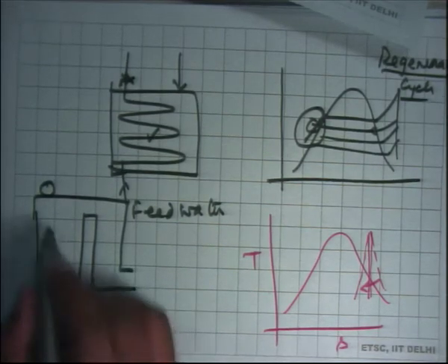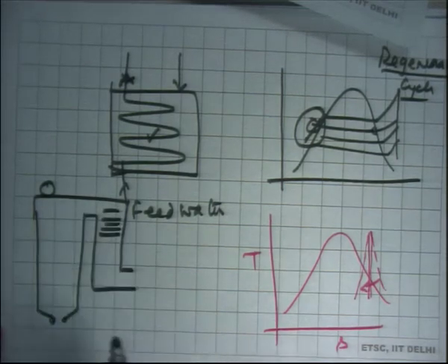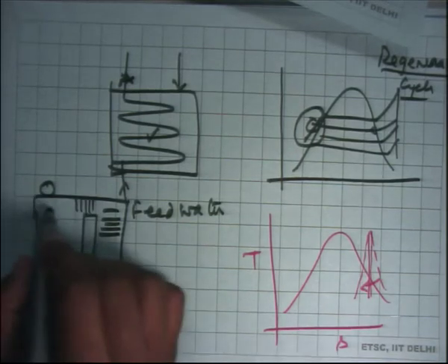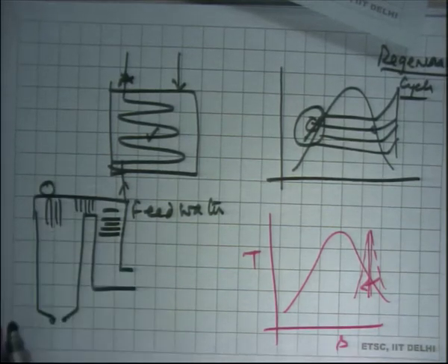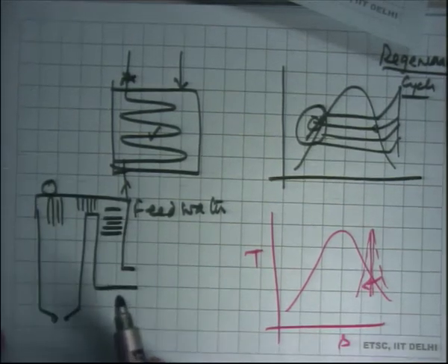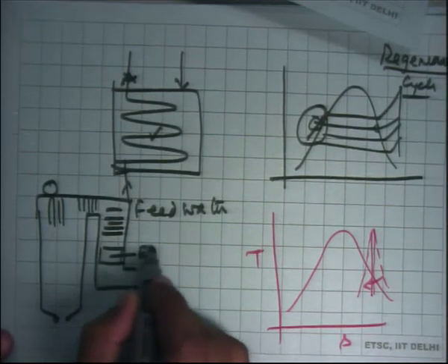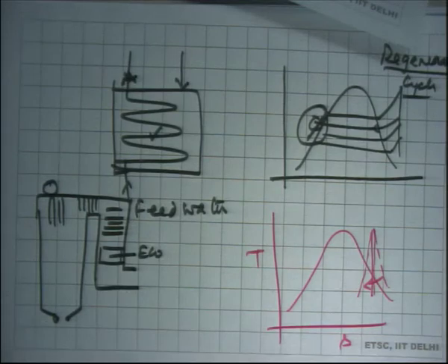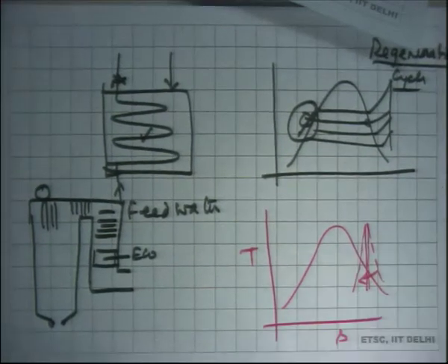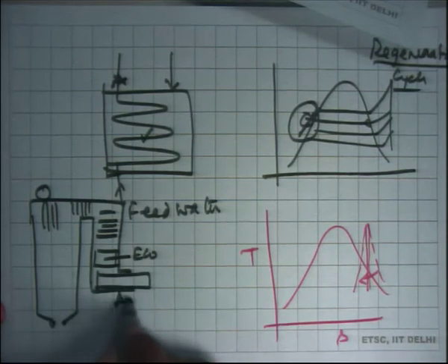So, now the low temperature superheaters and low temperature reheaters are here, the intermediate temperature superheaters and reheaters are here, the high temperature superheaters and reheaters are here. They are all pipes that are suspended from the roof of the boiler all over the place, and economizer is here, okay, and the gases that come out from the economizer run what is called an air preheater.